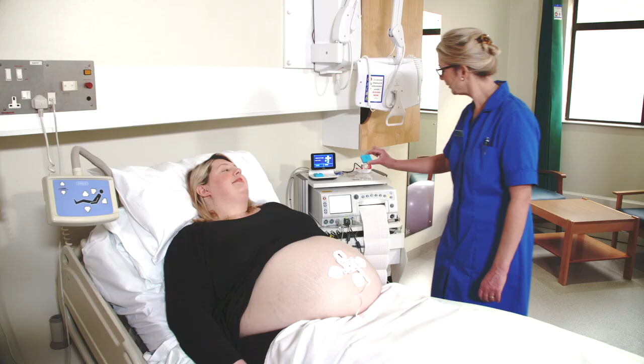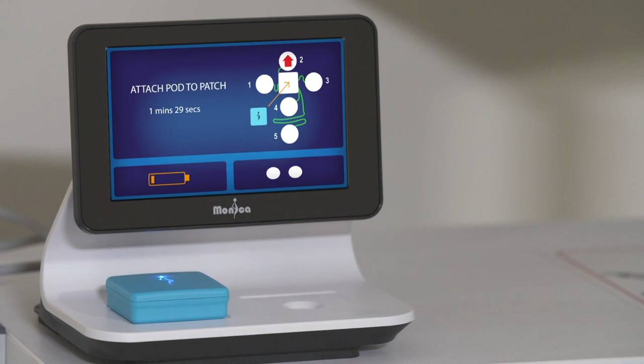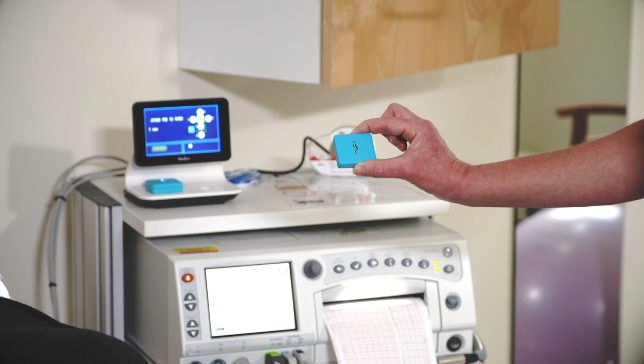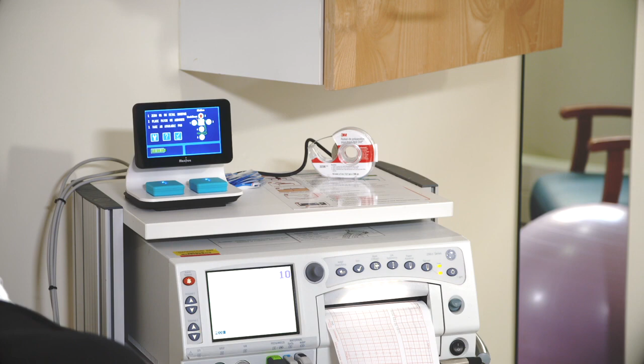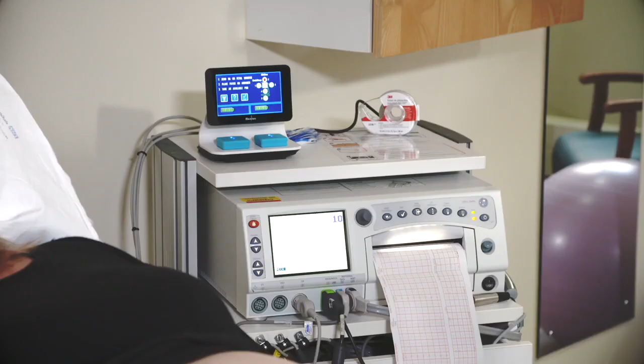Instruction 3. Take a fully charged pod from the charging bay. The Novii display will change to show a countdown, and both LEDs on the pod will start to flash alternately. If you do not place the pod in the patch clip, or place it back in the charging bay before the countdown has finished, an audio-visual alarm will be triggered asking you to return the pod to the charging bay. A pod can be charged from empty in less than 2 hours, so there is never a good reason to remove pods from the Novii system.